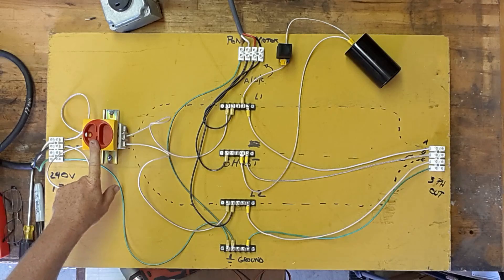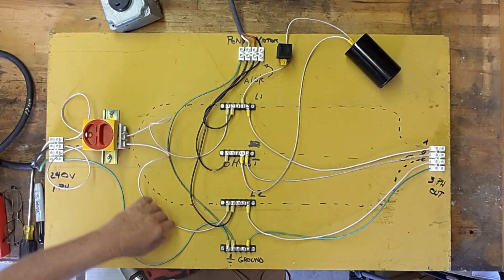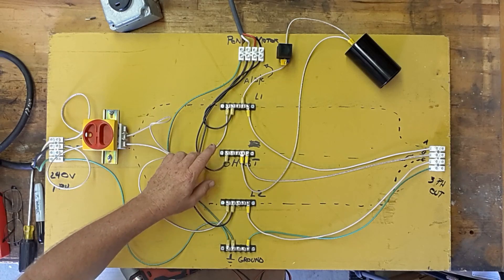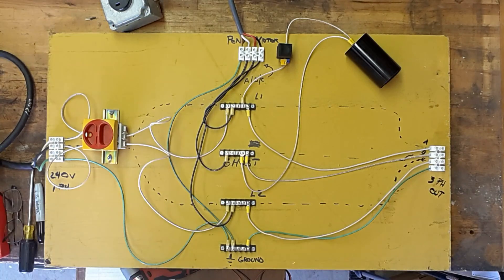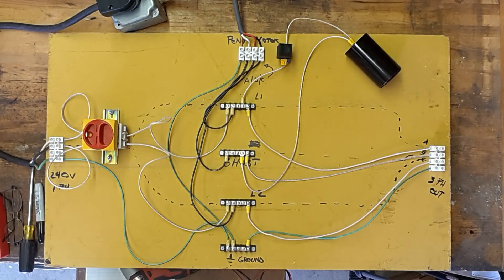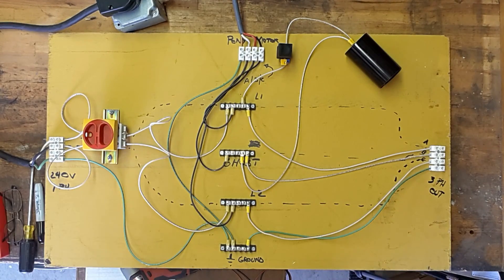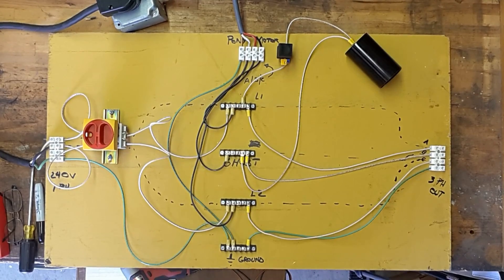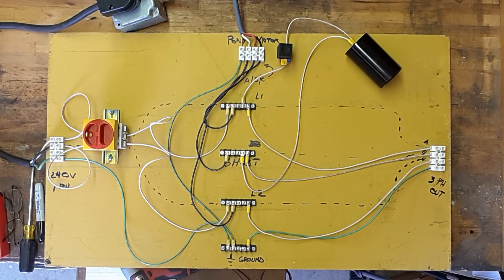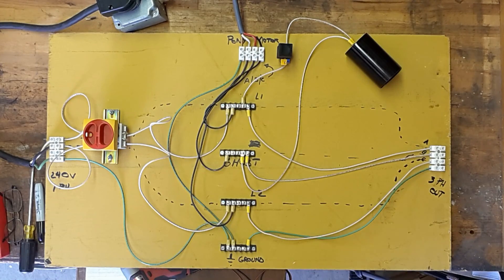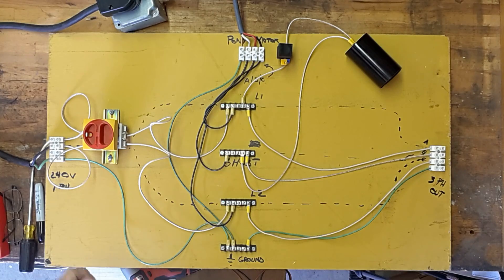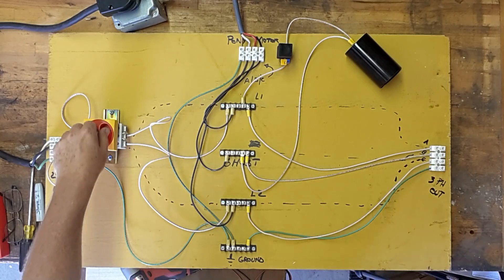Switch is off. Double checking the wiring. I think we're good. So we'll plug her in. Now I want you to listen because this is important. When I do it this way, the motor will have a hard time starting. And you'll think, oh, I need more start capacitor. But as the other legs come into more balance, when we add other capacitors, that all goes away. So when I turn this, you're going to hear the motor hum and then I'll hit the starter. Ready?